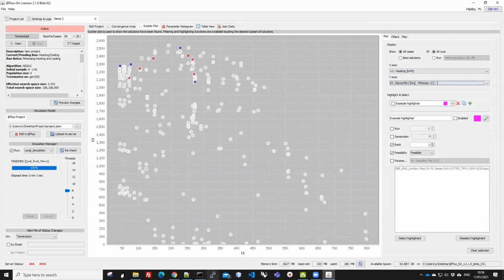So this is plotting heating comfort versus heating consumption. The comfort metric is shown as discomfort hours. In your simulation model, it can report the number of hours that are considered to be uncomfortable, and throughout the year, those are occupied hours. This is an office scenario, so in total there will be something like 3,000 hours that the space is in use.